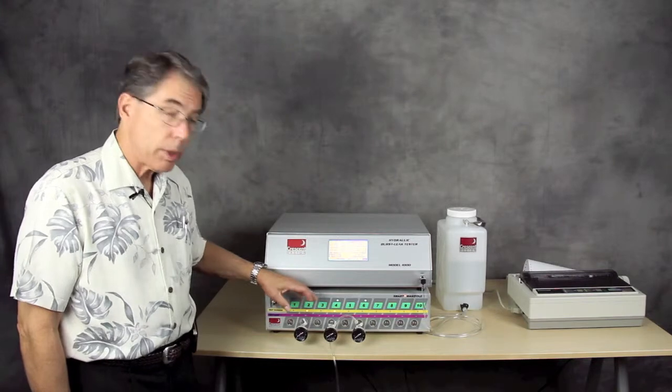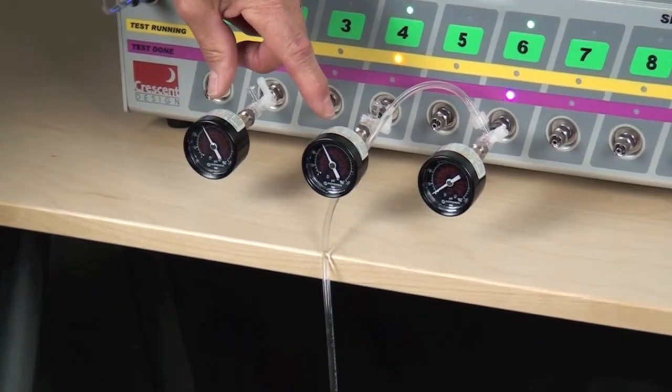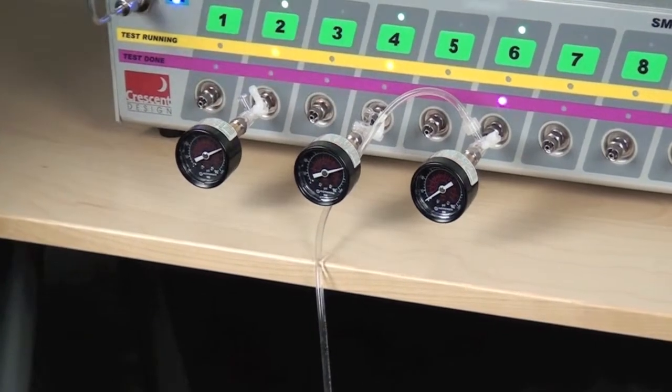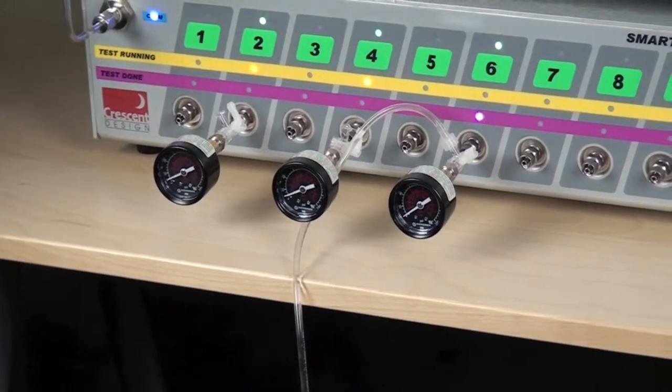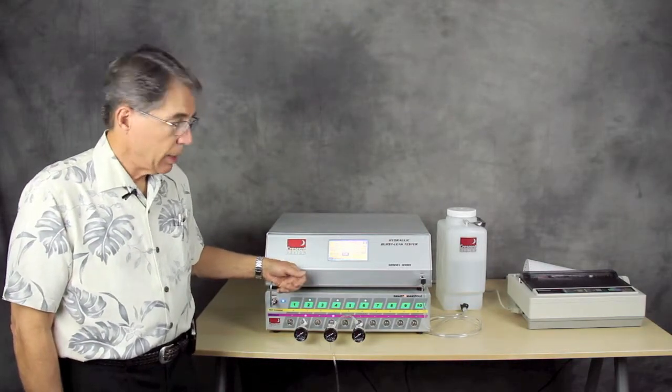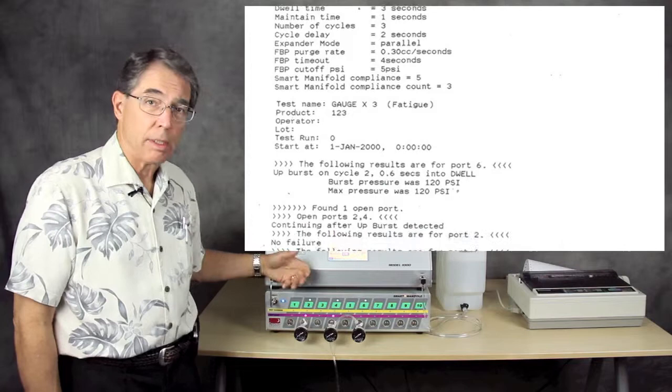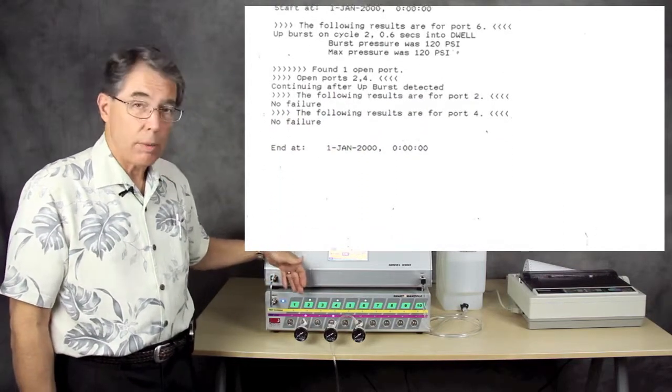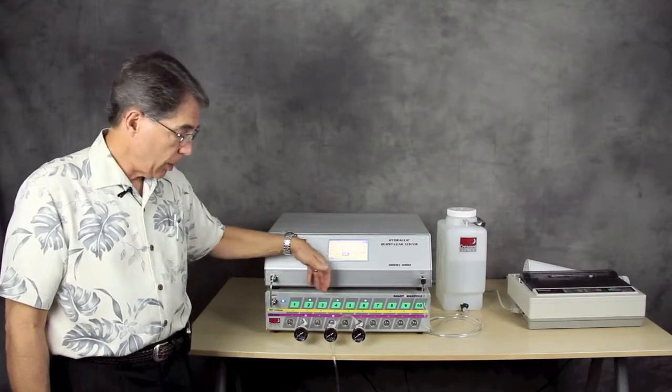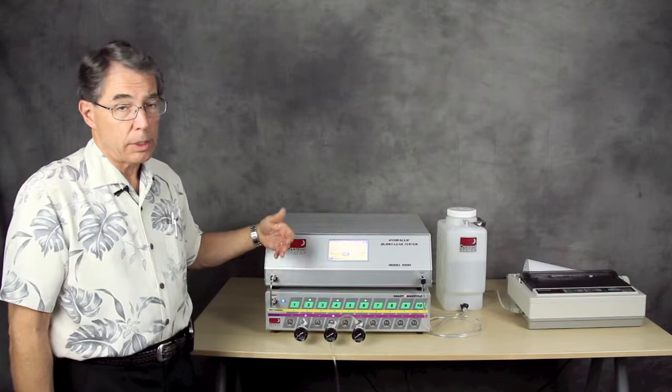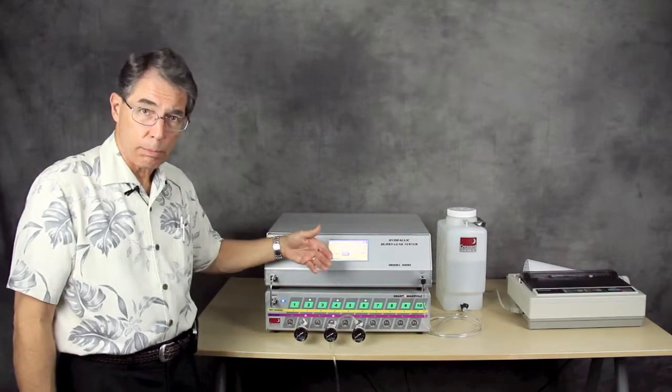It knew that it had three ports, only three ports selected, and there's still one cycle left to do. So you'll notice now it's going up for the third cycle to 120 for three seconds. And then it runs back down. And that is the end of the test. And the test results are now being printed on the printer over on our right. And that's the end of a parallel test. And you can see why we call it the smart manifold because it was able to determine which port had failed, stop the test, find the port, and then continue on either until all of the products have failed or until the program number of cycles have completed.